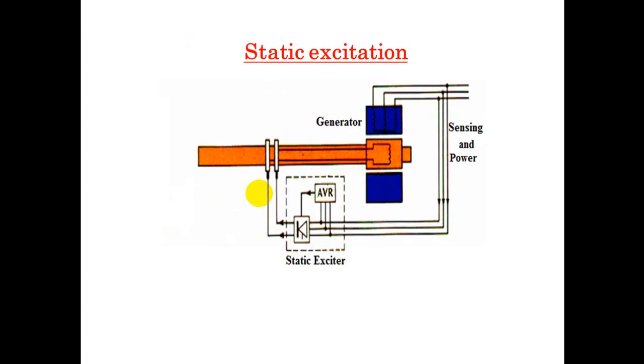The second method is called the static excitation. In the static excitation, the rotating DC exciter is replaced by a static electronic exciter. At start, same as for the conventional excitation, there is no power output of the generator, no DC current to give to the rotor winding. Two solutions for a small generator: this system is also using the remnant field magnetism of the rotor, building gradually the voltage up at generator output.